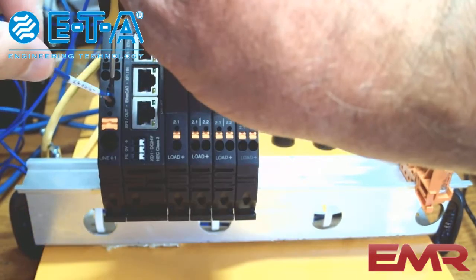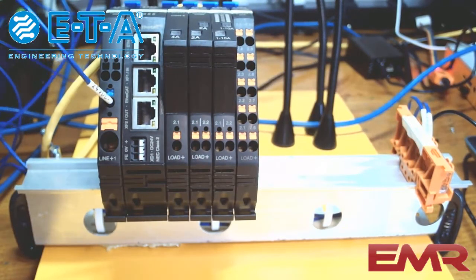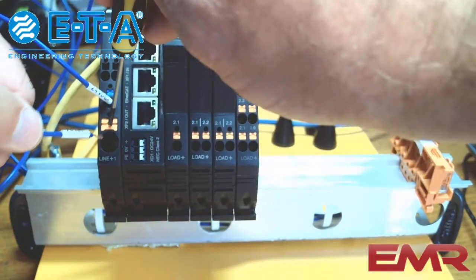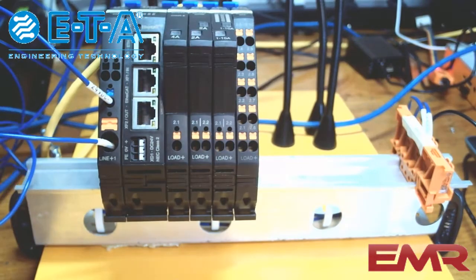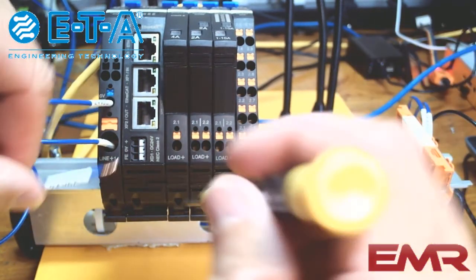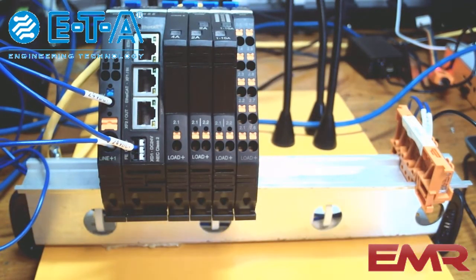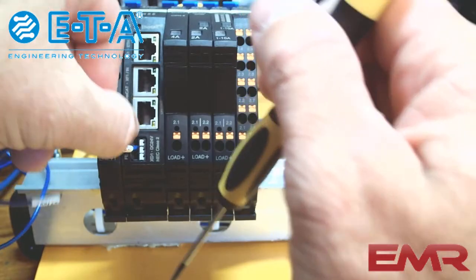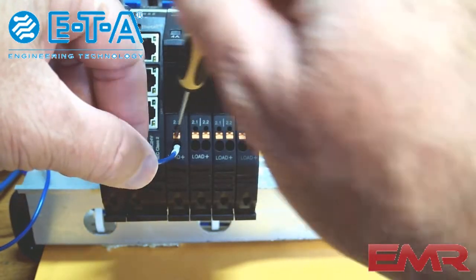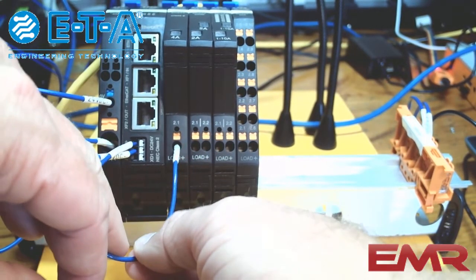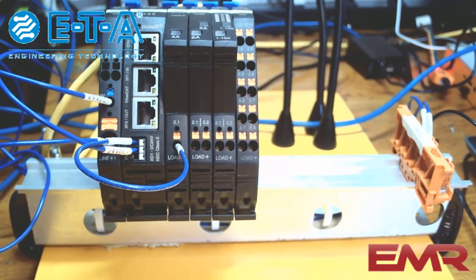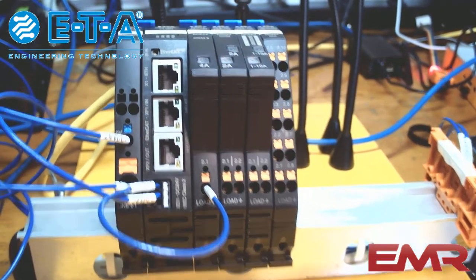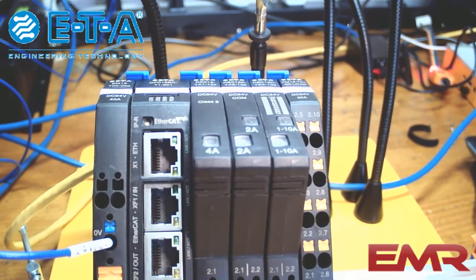For this quick demo, we've installed the breakers here, snapped them to the DIN rail. We're going to power the communication module from that first breaker in the row, and then we'll have 4 breakers that'll be part of our process automation. The first breaker there does not have communication. The communication module allows a separate power supply, so it's not powered from the bus like the breakers are. This will let you power it by a different DC source or a battery backed up source.